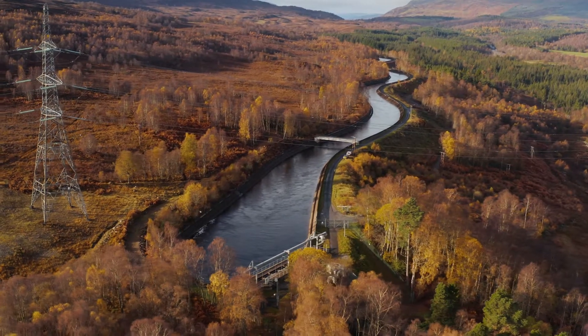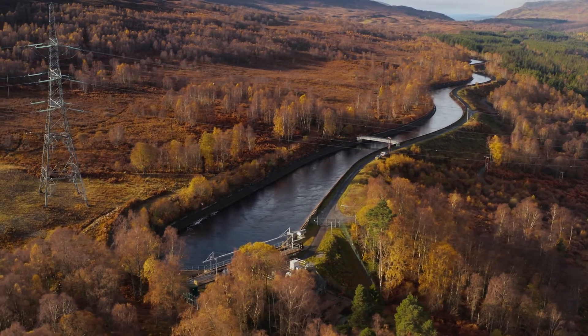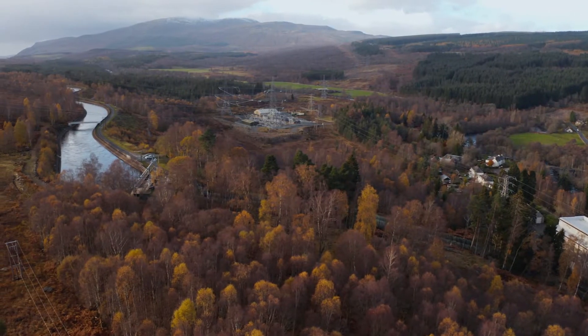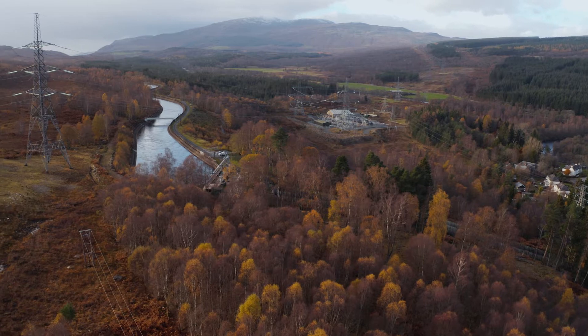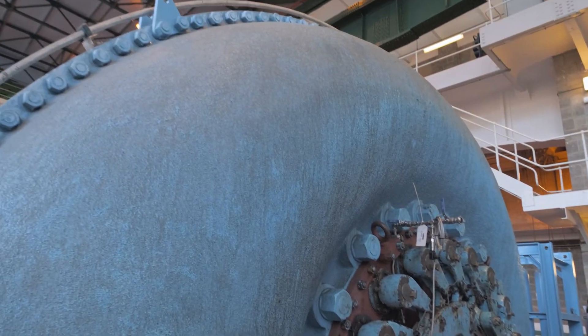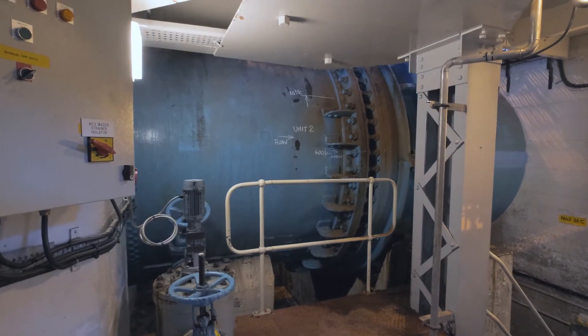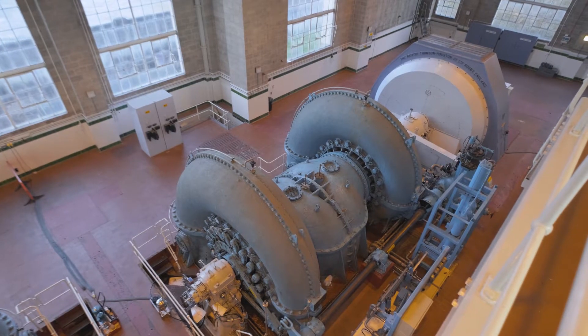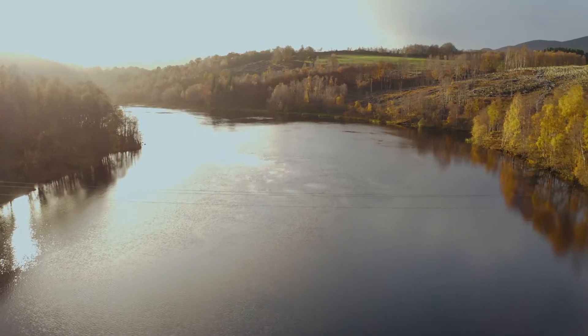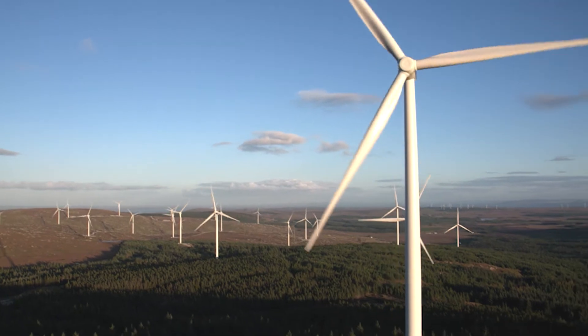Tummel provides the ability to start and stop as required with relatively low run-up and shutdown speeds. We can be producing 17 megawatts within 40 minutes. As the Hydro Operation Control Centre gets a call from National Grid that something has happened elsewhere within the grid, these machines can come on and start to support the grid. Tummel also provides flexibility to the National Grid through its sheer bulk — the machines themselves weigh approximately 120 tonnes — which absorbs lumps and bumps within the network from small wind or solar coming on, providing stability to the grid.